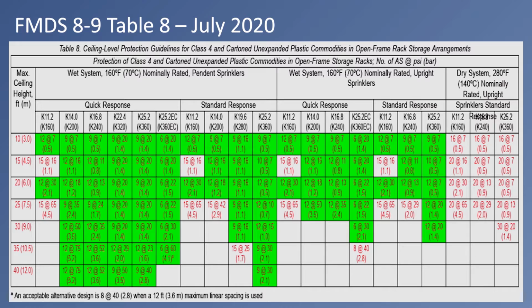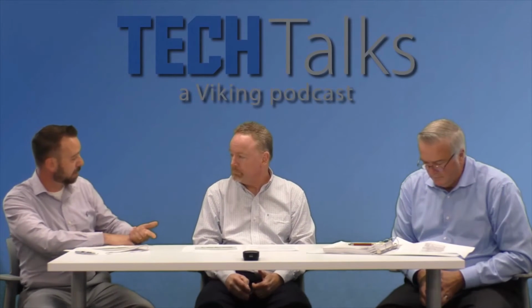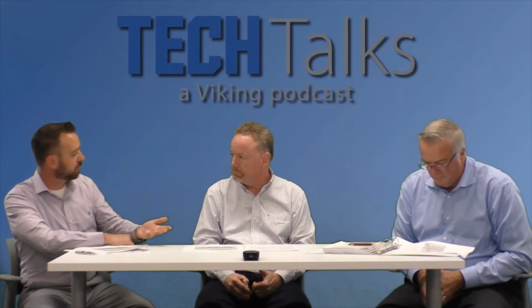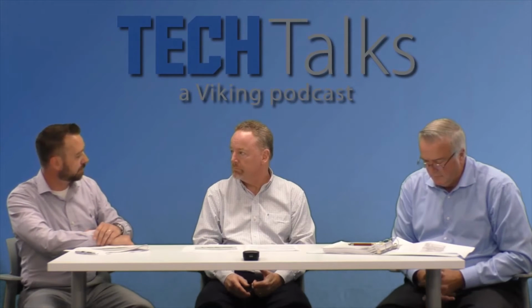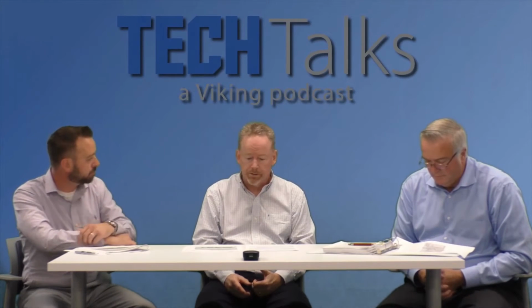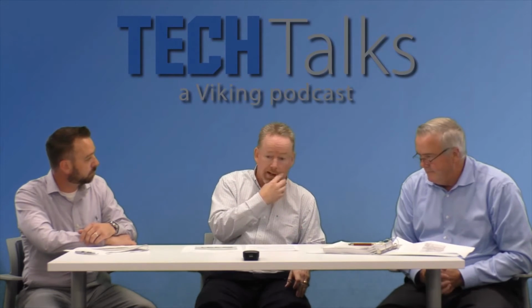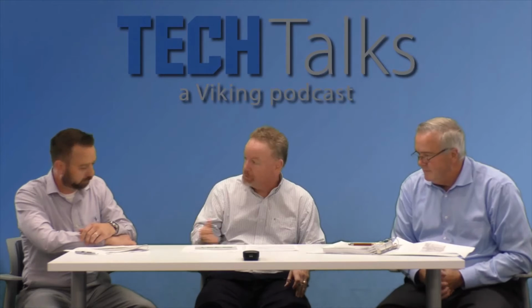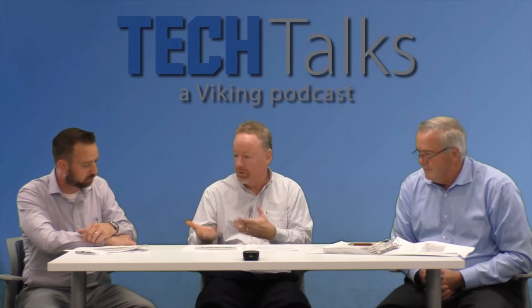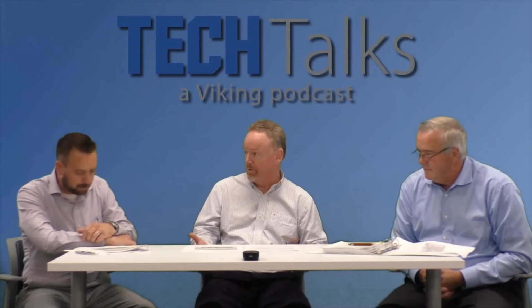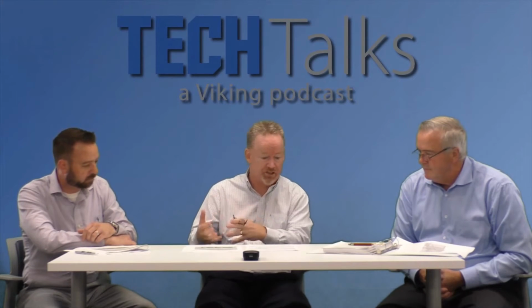Okay. So in that case, that's where we get into 3-0, which we'll look at a little bit later and see how that's going to affect how many sprinklers you might have to calculate on a branch line outside of the old 4 sprinklers on the 3 most remote branch lines. Okay. So the impact there is obvious: by reducing the number of sprinklers, the pressures of those sprinklers, I mean, we are reducing system demand. That's just a question of hydraulics. That's one of the big impacts, is that's changed a lot.